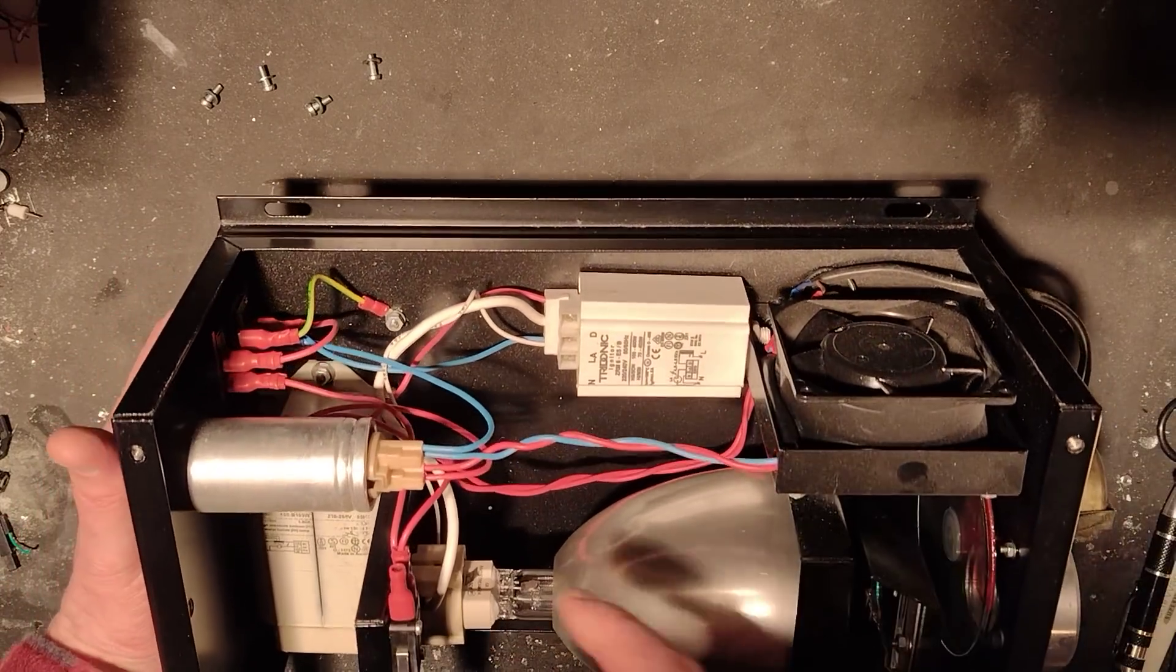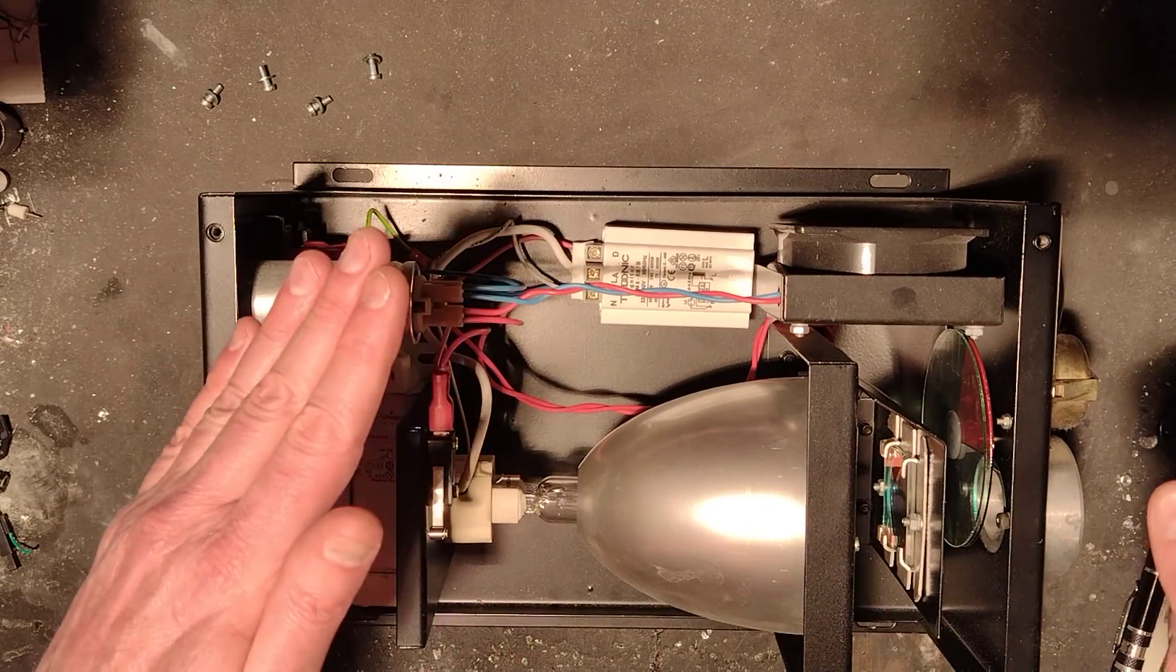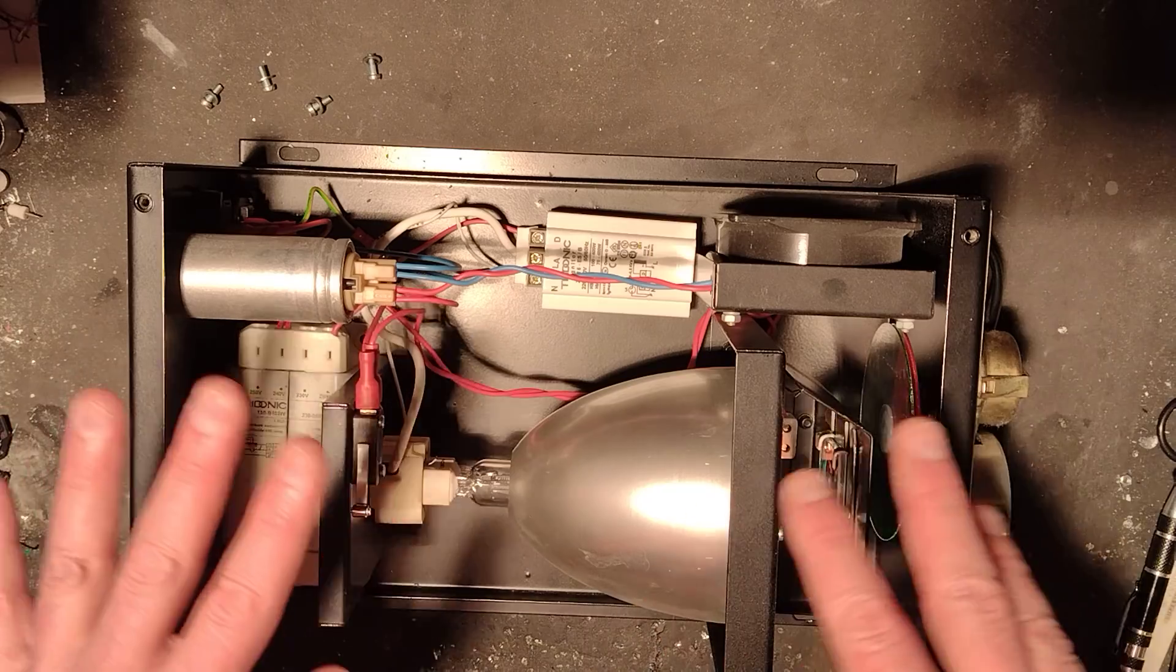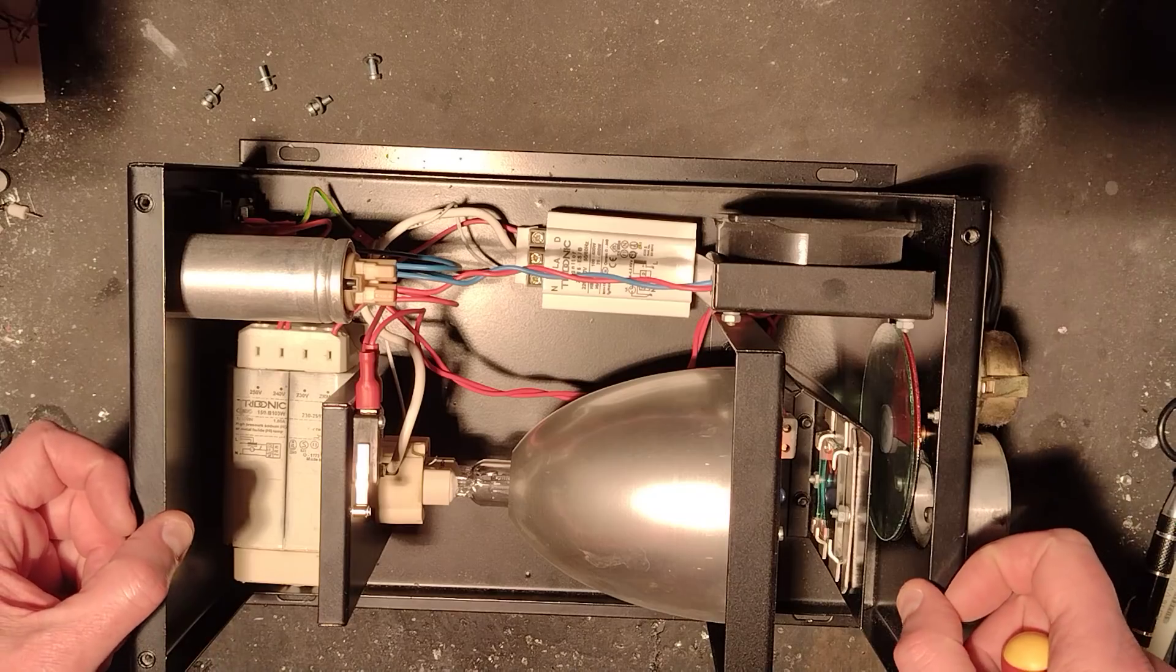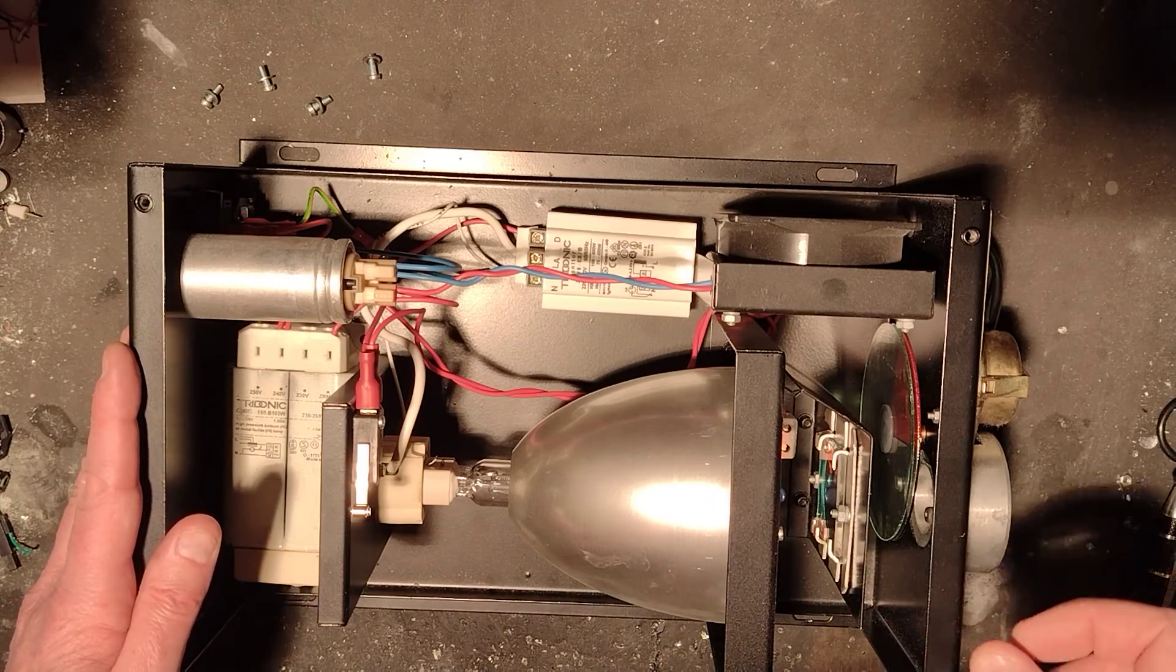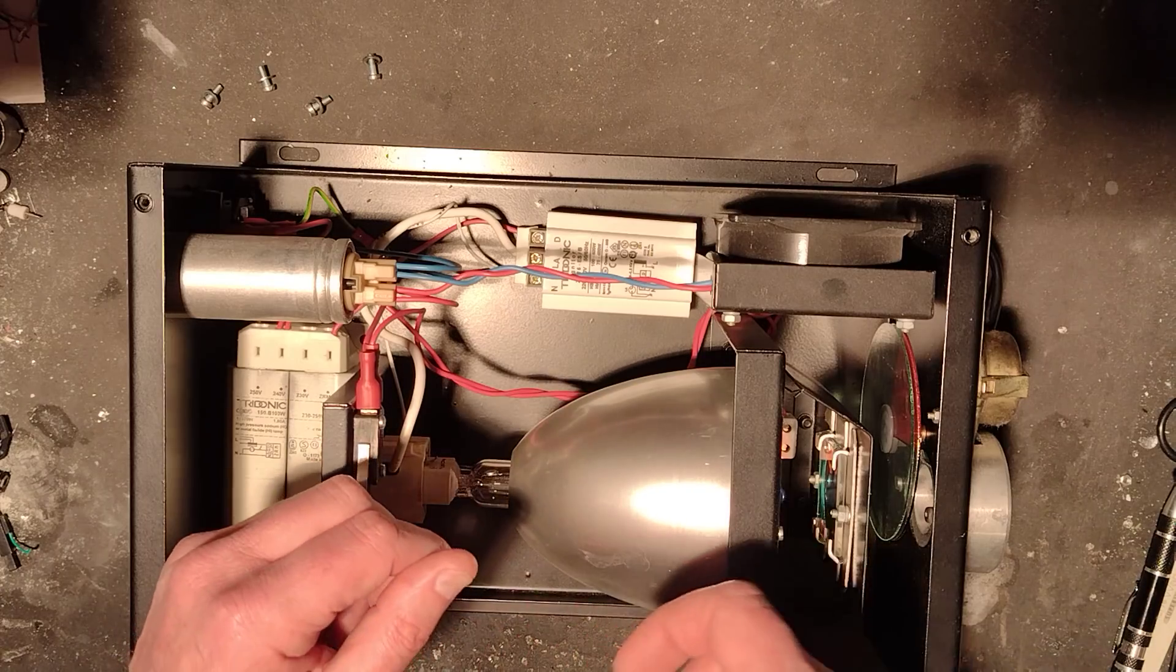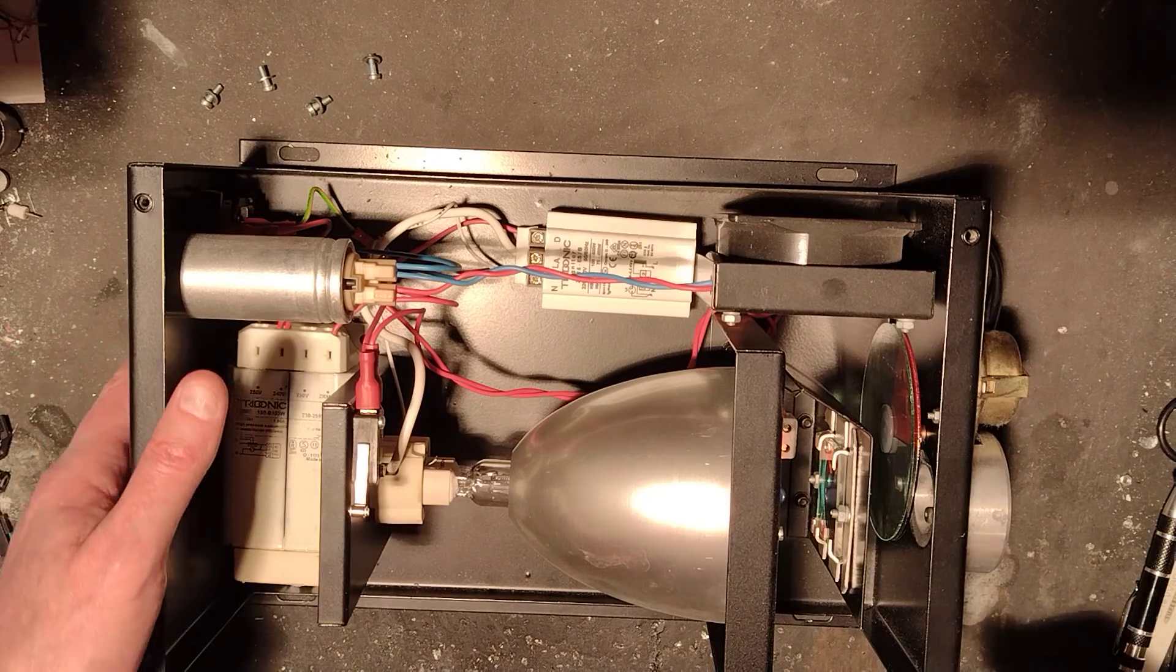The on off switch then comes up to this micro switch here which is a safety switch. If you take the lid off, it will kill some of the power in the unit. It shouldn't be treated as being a complete isolator. It's just what you might call an idiot switch, just for those people who attempt to fix things. It means that if you're faffing around trying to get the lamp in here and you press that, you could be in for a surprise because this little thing down here puts out 4000 volts to ignite the lamp.